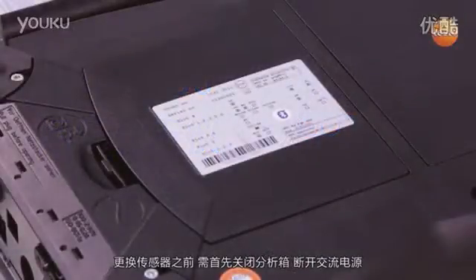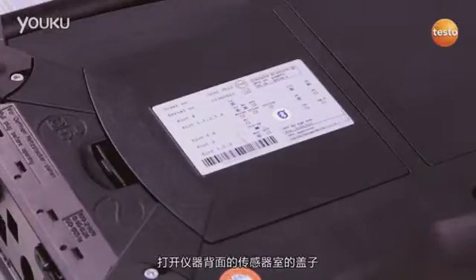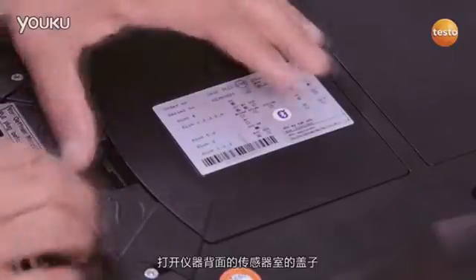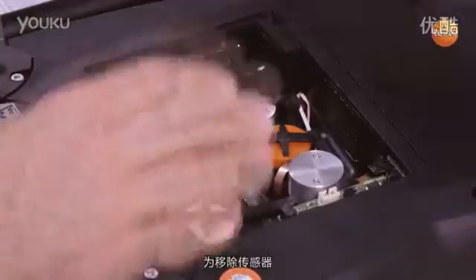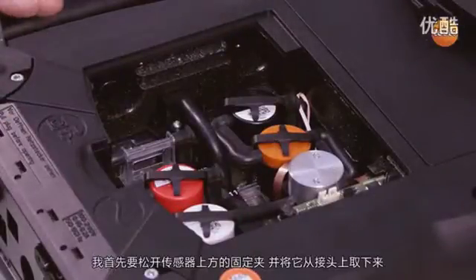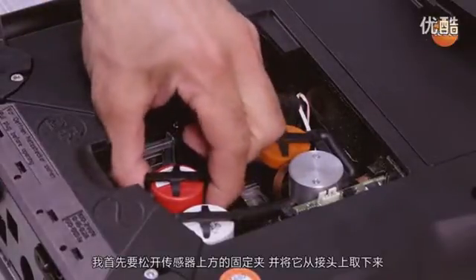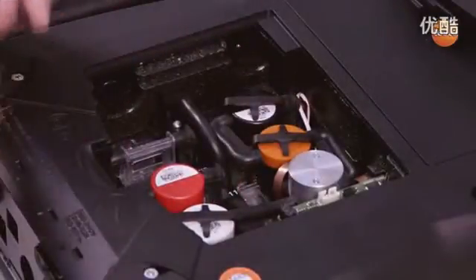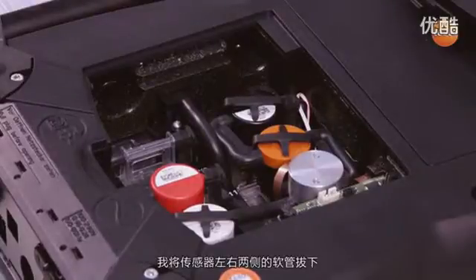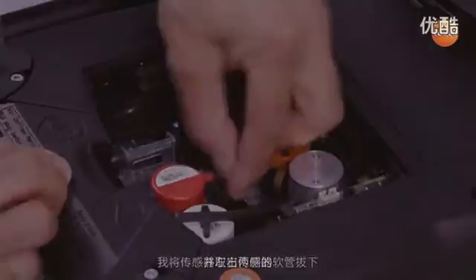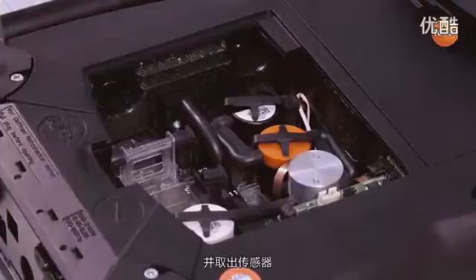Before I can replace the sensors, I have to switch off the analyzer box and disconnect it from the power grid. I open the sensor compartment cover on the rear of the instrument. In order to remove the sensor, I have to release the clip over the sensor and remove it from its fittings. I disconnect both hoses on the left and right of the sensor and remove the sensor.